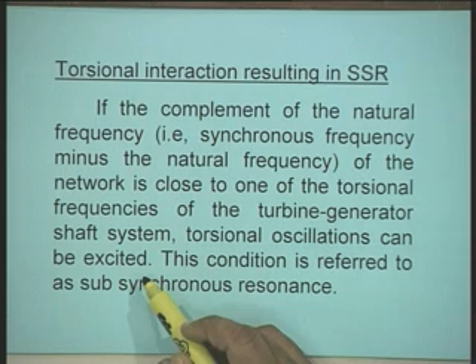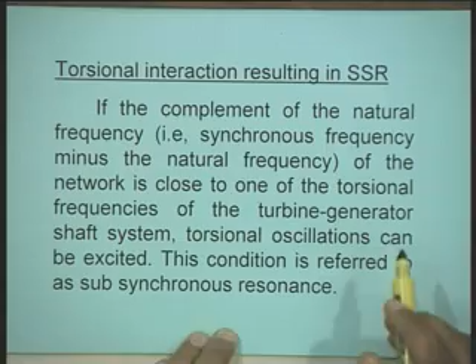This is what we have already seen. This condition is referred to as subsynchronous resonance. We always use the word complementary frequency, because the slip frequency plus the natural frequency, the sum, is equal to the system frequency. In case the complement of the natural frequency is close to any of the torsional modes, then the oscillations can be excited, and this phenomenon is called the SSR phenomenon.